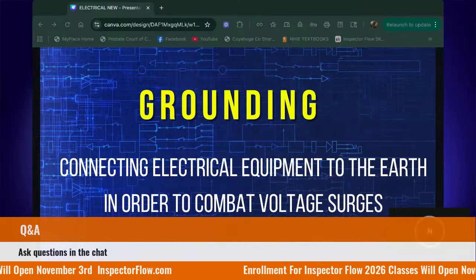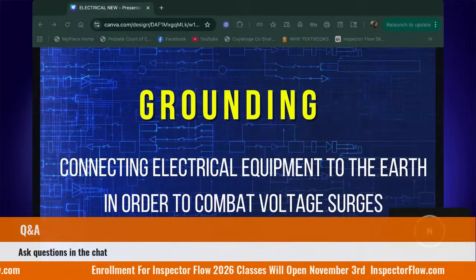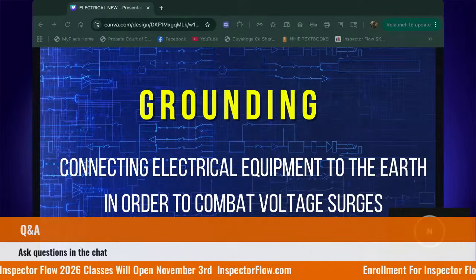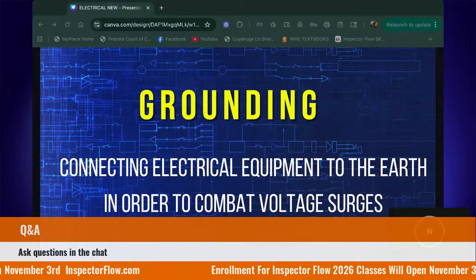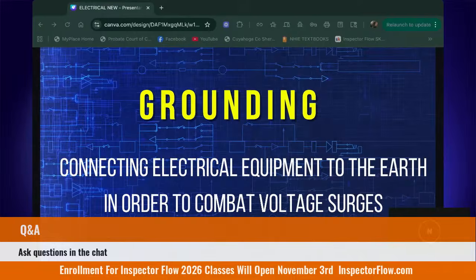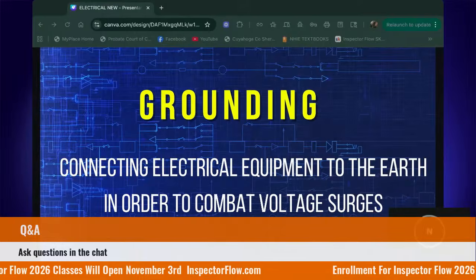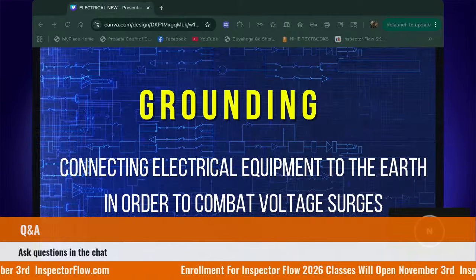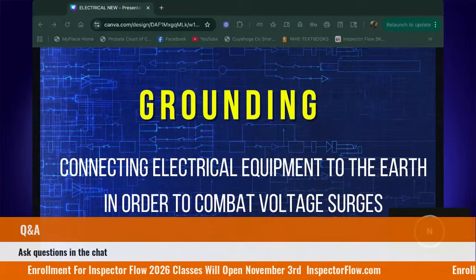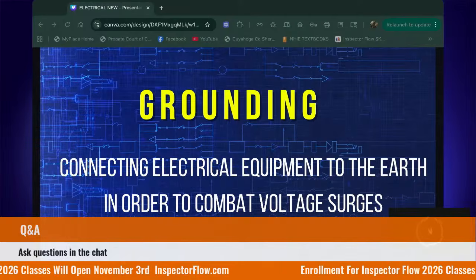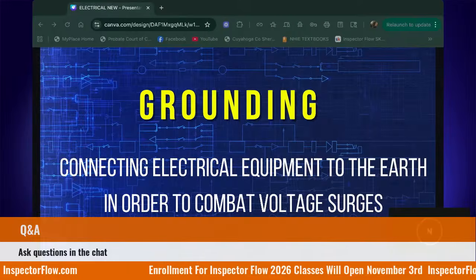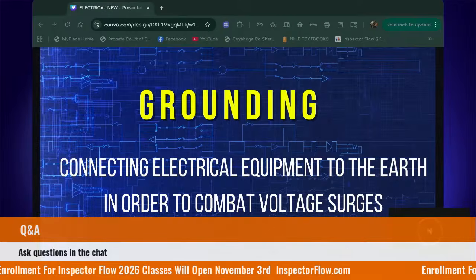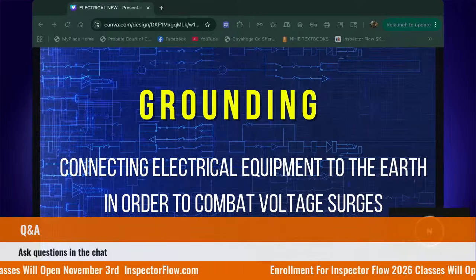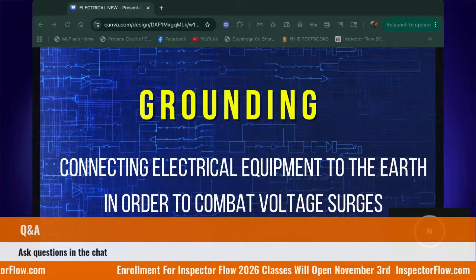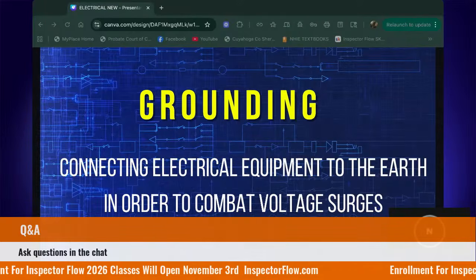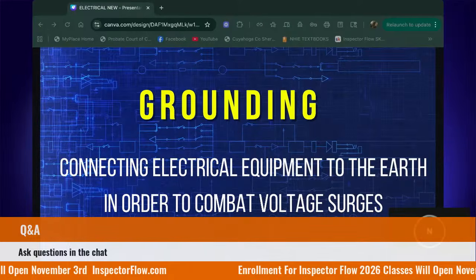So this protects again all of the metal parts, our fixtures, our outlets, the frames of our appliances that again are metal and could become energized. Our equipment grounding is protecting those. These are where we have our green or our bare copper wires, those equipment grounding conductors. So if a hot wire were to ever touch metal, the grounding wire carries that current straight back to the panel through the bonding jumper. And then the breaker trips and kills the power. So that way the person doesn't become the path to ground. Because again, electricity doesn't care where, it just wants to flow. And if you are a conductive material, you could become a part of the path. Okay?